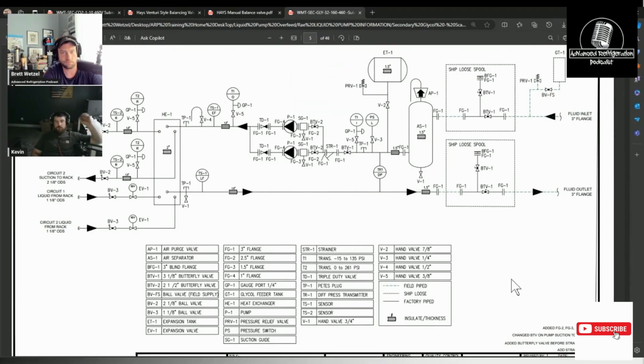Before you go to start this, scan the QR code inside the unit, and it's going to bring up an expansion tank setting guide. Now it's a little weird how they're doing it - they're figuring out some of the math for you. Now mine was on the ground, so my expansion tank setting was way higher. They want to run a 10-pound static pressure all the time.